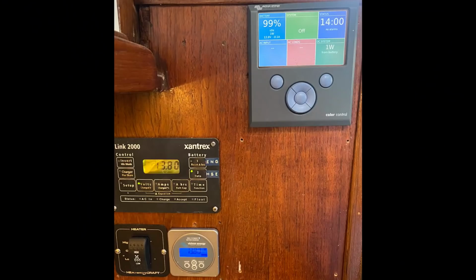One really important thing when you install lithium LiFePO4 batteries is that you can monitor the system. Yes, the BMS takes care of a lot, and setting your chargers takes care of a lot of problems too, but it's really good to be able to glance at the status of your batteries - the amperage coming in and going out, the voltage, the state of charge. It's important to keep an eye on those and make sure everything's doing what it's supposed to.